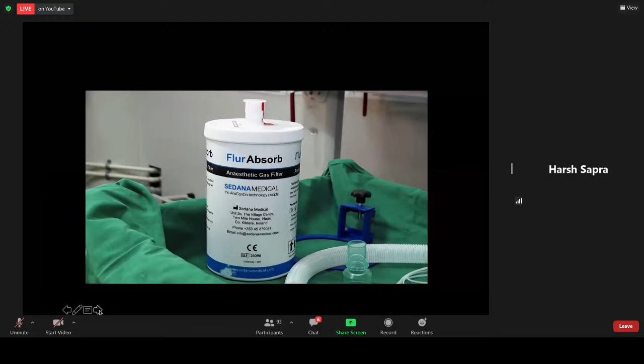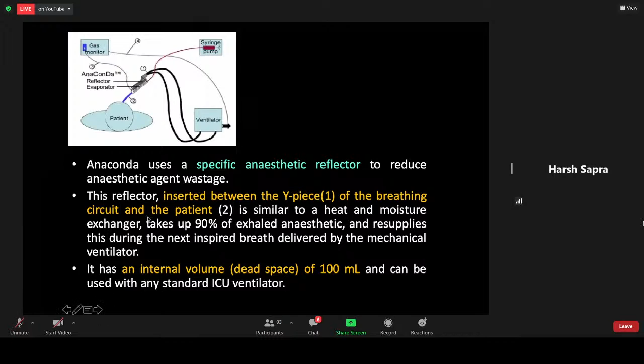So Anaconda uses a specific anesthetic reflector to reduce anesthetic agent wastage. The reflector inserted between the Y piece of the breathing circuit and the patient, as I showed earlier, is similar to a HME and takes 90% of the exhaled anesthetic and resupplies this during the next inspired breath delivered by the mechanical ventilator. It has an internal dead space of around 100 ml. So obviously it can be used with standard ICU ventilators.